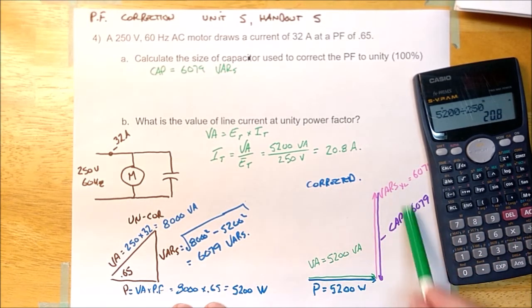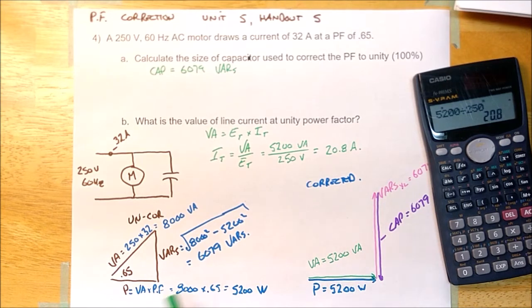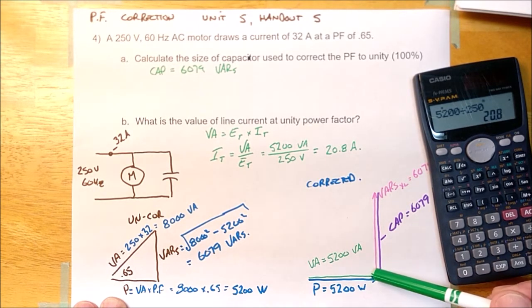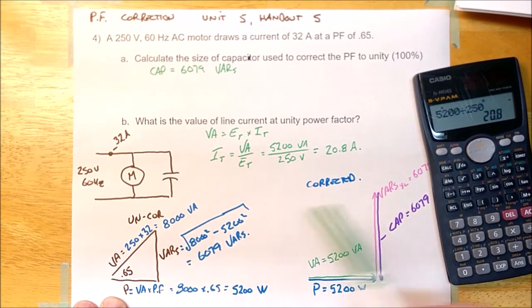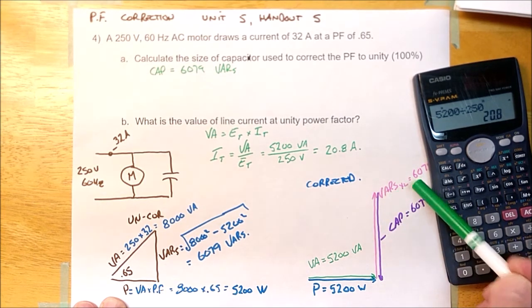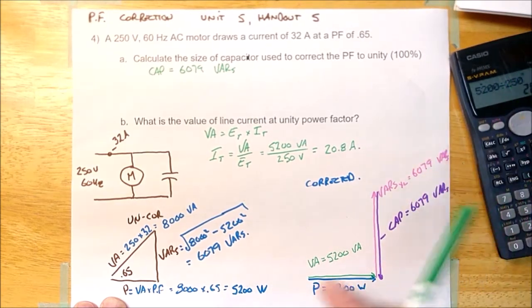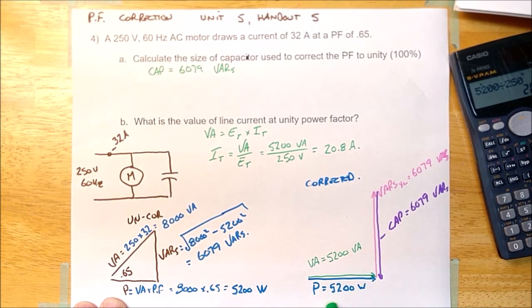The way you draw this power phasor diagram is you start with the true power because it is going to be the same as the true power was before correction. So that blue line first. Second line is this VARs. It is all the reactive power due to the inductor. Then you can add your cap. It's going to be equal to that. And then you can add your VA. It is going to be equal to that.